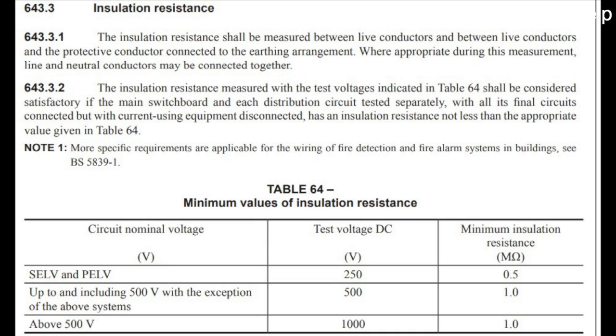Regulation 643.3.2 basically tells us to look at the table below, and basically telling us that we need to test our low voltage circuits at 500 volts, and the minimum insulation resistance should be 1 megaohm. Now what it does tell us is we should test every distribution board and distribution circuit with all electronic equipment removed. Therefore, it is important to remove all the equipment vulnerable to test, because what we would like to do is test every single circuit in that distribution board in one go, rather than keep disconnecting each circuit separately.